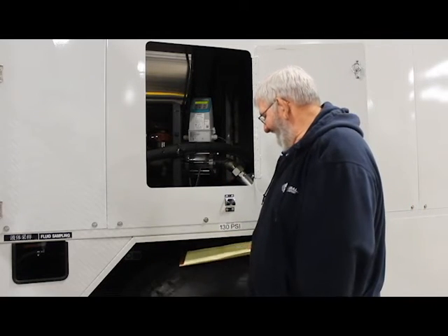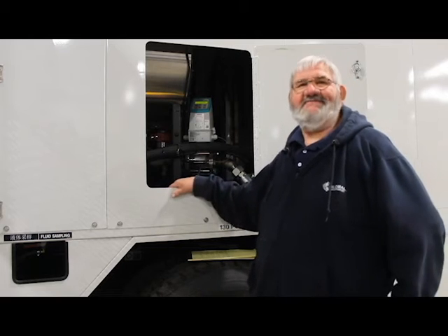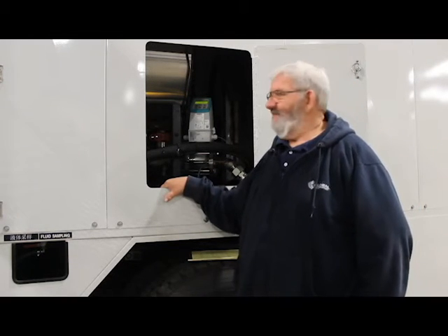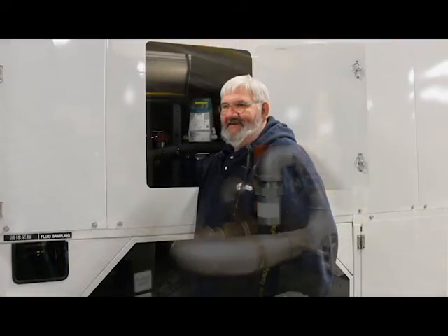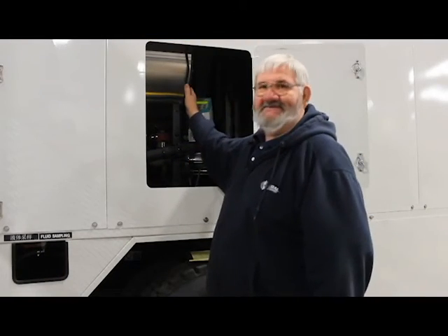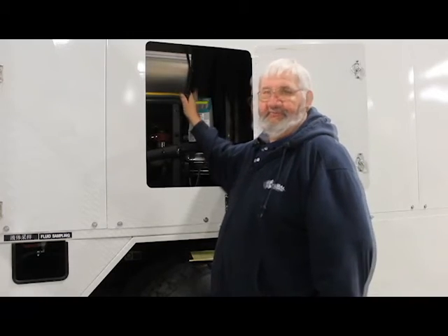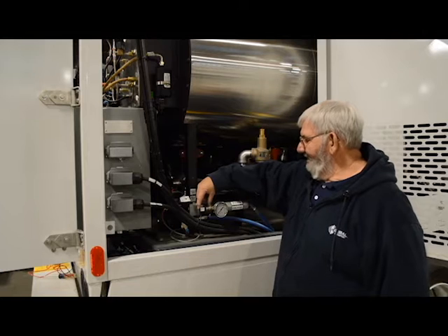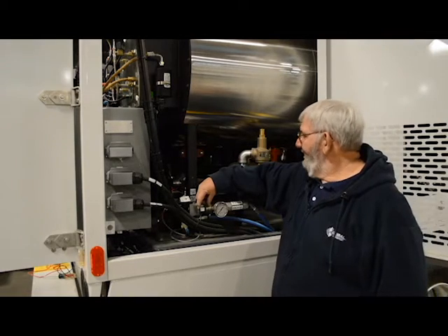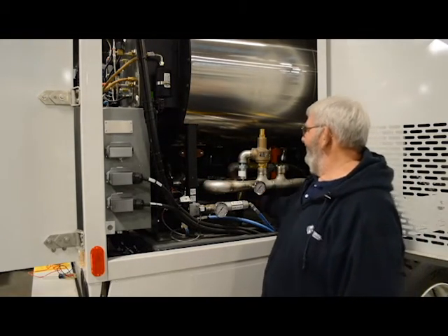Now to start off with, you need to know the locations of the RTDs. What RTD stands for is remote temperature detection. Now if you look right back here, this little gray half ball shaped sensor is your inlet RTD. It's the inlet because it is on the inlet side of the heater, which is the side closest to your fluid tanks. This little device right here is your fuel pressure transducer, and then your outlet RTD is located back here on the outlet side of the heater.